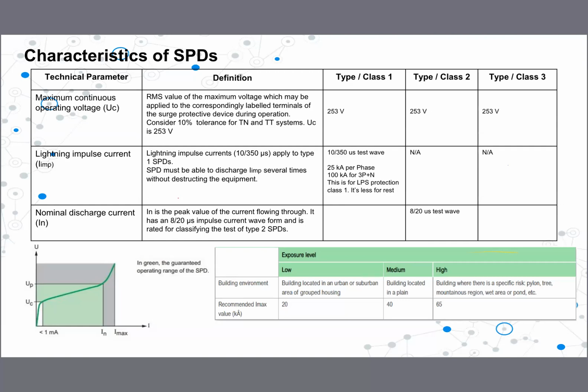So the surge protection device we install in the electrical system. What is maximum continuous operating voltage, or UC? It means that is the RMS voltage value applied across the terminals of the surge protection device, right? So in our system, our RMS value across the terminals in one phase is 230, right? But we use here a 10% safety margin for the surge protection device, then it becomes 253 volts. Therefore, the UC value of the surge protection device that we use in our system should be 253 volts, right?